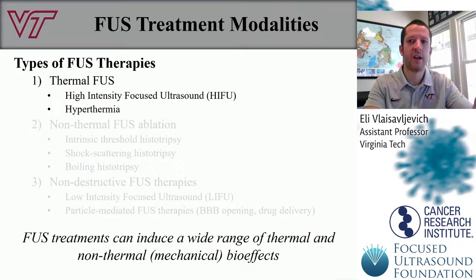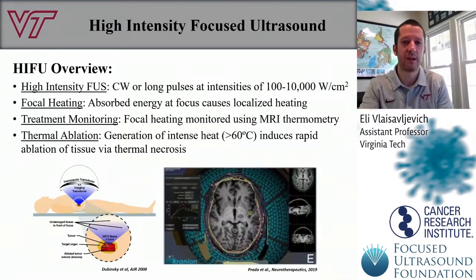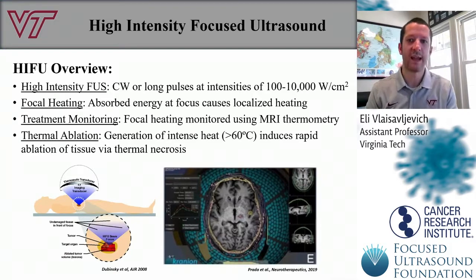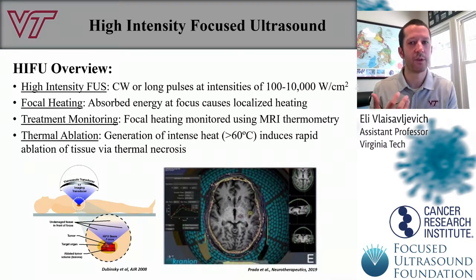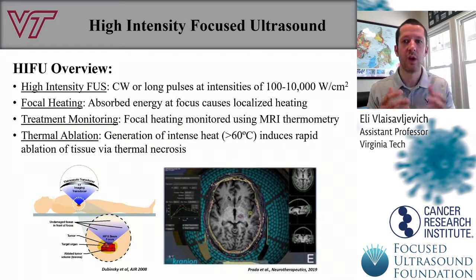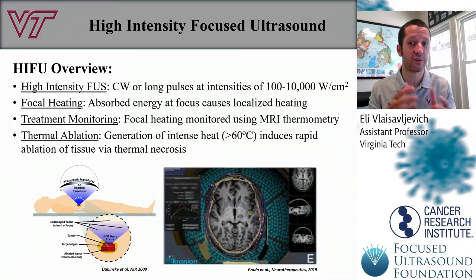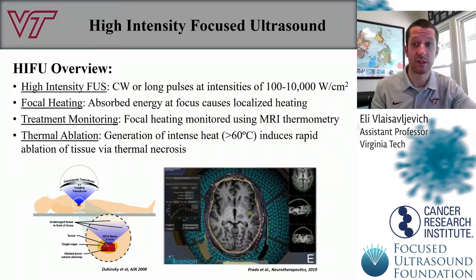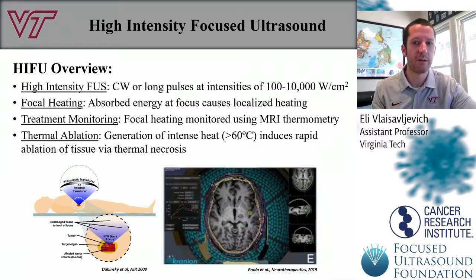First, we're going to be looking at thermal therapies. The largest body of work here is high-intensity focused ultrasound, or HIFU, which has been in development for a long time. HIFU uses continuous wave pulsing or high duty cycles at very high intensities, ranging from 100 to 10,000 watts per centimeter squared, focused to a single point in the body, resulting in the rapid heating of the target tissue to greater than 60°C, causing thermal ablation of the target.